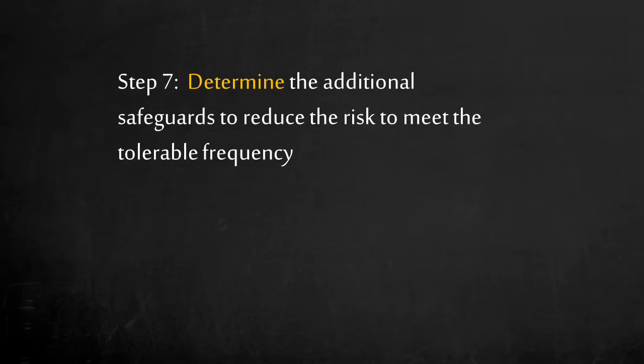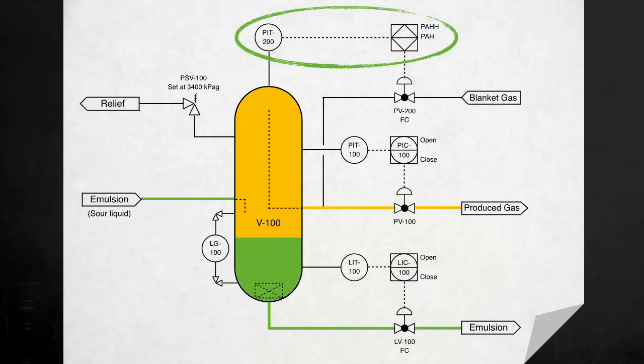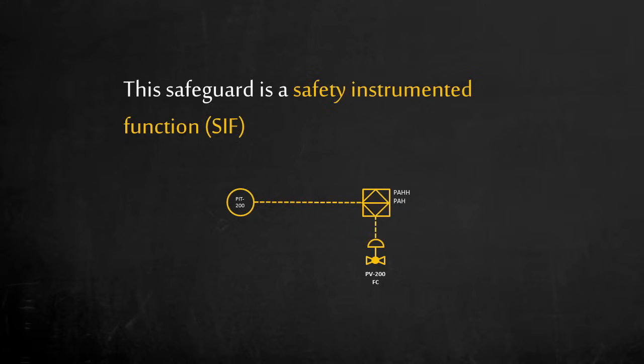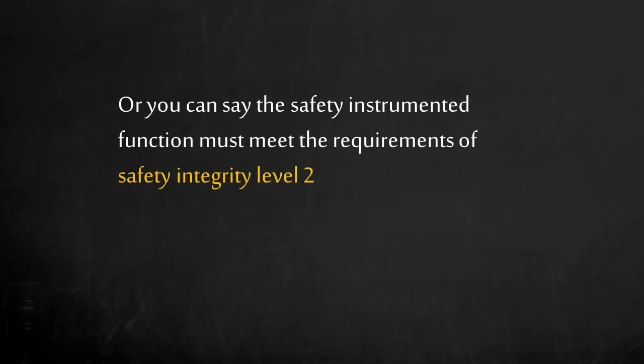Step 7: determine the additional safeguards to reduce the risk to meet the tolerable frequency. We can add an independent high pressure shutdown on the blanket gas as a safeguard to eliminate the high pressure source. We added a safeguard consisting of a sensor, logic solver, and valve — the final element. We call this a safety instrumented function: an automated safety action to bring the process to a safe state. The current system is 100 times more likely than acceptable, so the safety instrumented function needs to reduce the likelihood by a factor of 100, with a probability of failure on demand less than 1%. Since this safety function must reduce the consequence likelihood by 100 times, it must meet the requirements of Safety Integrity Level 2.